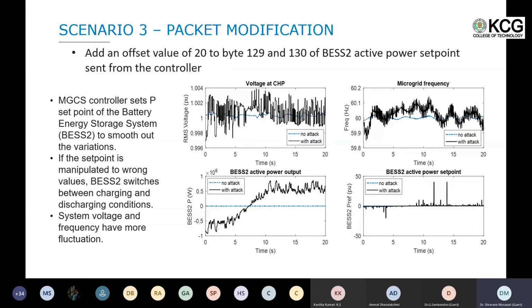Its controller and its inverter receive information from the MGCC, the microgrid control, as well as its local control. So if I add an offset to the microgrid controller's input, because the battery is not aware of what is happening globally, it depends on the microgrid controller's response, the microgrid controller's information. The battery thinks, okay, I need to discharge a bit more. So that is what is created here.